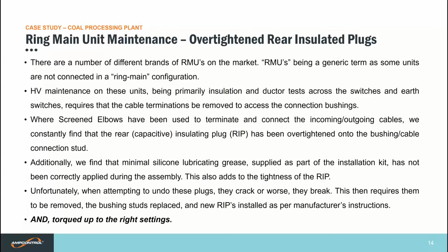Moving on to our second case study. This one's a common one that we find, a ring main unit maintenance, and the rear insulating plugs have been over tightened. Apologies for that. There are a number of brands of RMUs on the market, RMUs being a generic term, as some units are not connected in a ring main configuration. But basically, you've got a cable coming in and a cable coming out.